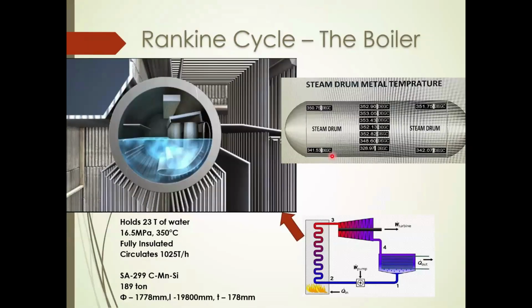Now, let's move on to the boiling phase. The boiling phase involves pipes and tubes that run through the furnace, getting energy from the burnt coal and, of course, from the flue gas. In the middle, you have a specific equipment known as the steam drum. The steam drum stores steam generated from water tubes and, of course, acts as a phase separator. This is where the steam and water separation occurs.